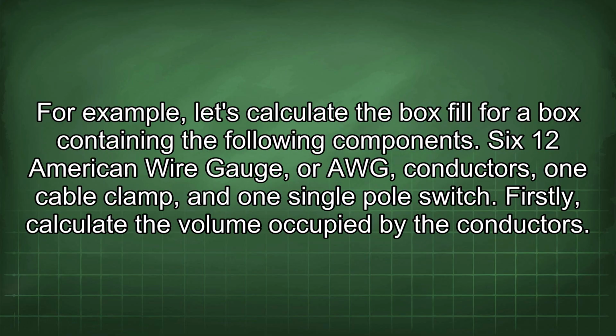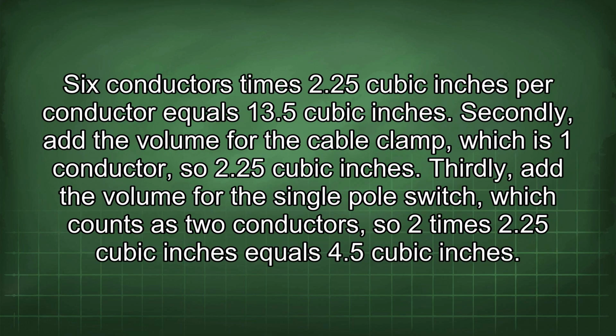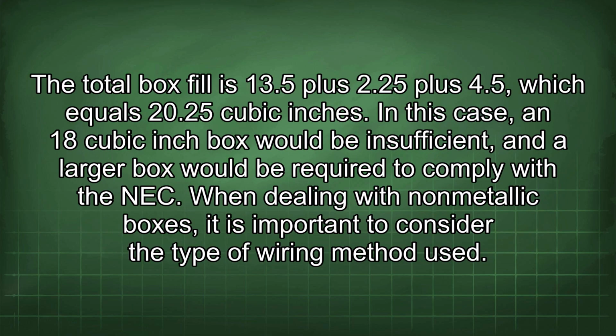For example, let's calculate the box fill for a box containing the following components: 6 12 AWG conductors, 1 cable clamp, and 1 single pole switch. Firstly, calculate the volume occupied by the conductors. 6 conductors times 2.25 cubic inches per conductor equals 13.5 cubic inches. Secondly, add the volume for the cable clamp, which is 1 conductor, so 2.25 cubic inches. Thirdly, add the volume for the single pole switch, which counts as 2 conductors, so 2 times 2.25 cubic inches equals 4.5 cubic inches. The total box fill is 13.5 plus 2.25 plus 4.5, which equals 20.25 cubic inches.